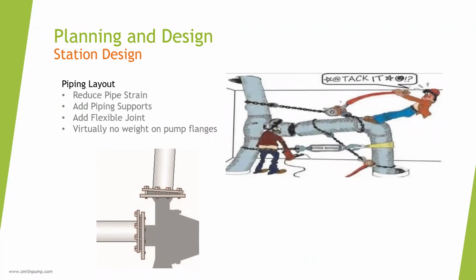So when it comes to pipe strain, I tend to think of pumps like they're made of rubber instead of steel or cast iron. It's because pipe strain can actually bend and warp the pump case or discharge head on vertical turbines. This throws the line shaft out of alignment and causes reduced bearing life and seal life.